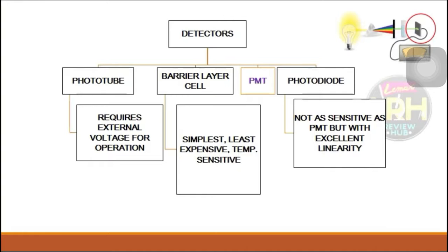So we have the detectors or photodetectors. Light passing through the analyte strikes a photodetector. Electrons in what we call the semiconducting material are excited proportionally to the wavelength of the light striking the photodetector. As we increase the light intensity, it generates more electrons, translating to a higher current that is received by the signal processor. Or in other words, the photodetector converts radiant energy to electrical energy.